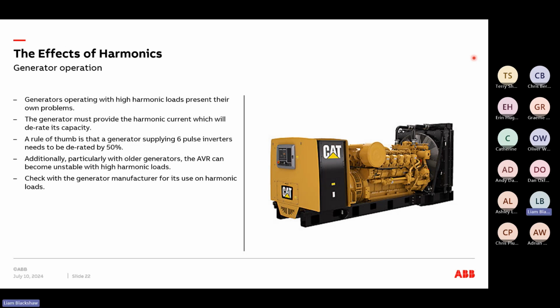But in addition to that, if we're looking at older generators, for example, the voltage regulation system can become unstable with high harmonic loads. So it's always worth checking with the generator manufacturer for its use on harmonic loads, just to make sure that there are no tolerances that you have to adhere to, at least anyway.